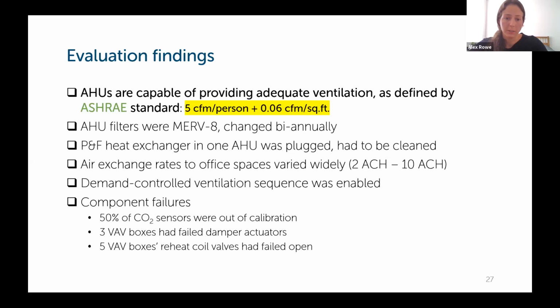In addition, the contractors noted some component failures. So 50% of the CO2 sensors were out of calibration. So even if DCV, demand control ventilation, was enabled, it wouldn't function properly. 3 of the VAV boxes had failed damper actuators, so they were not able to modulate the outside airflow as needed. And 5 of the VAV boxes' reheat coils or coil valves had failed open, so they were overheating the space, which is not good for the temperature component of good indoor air quality.